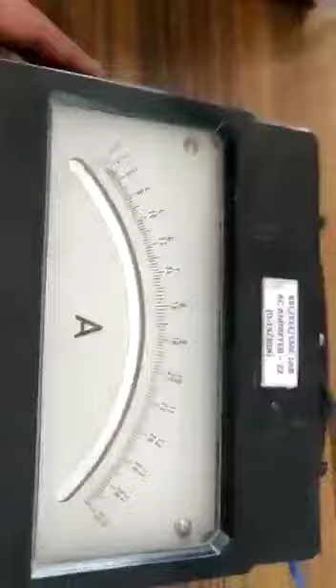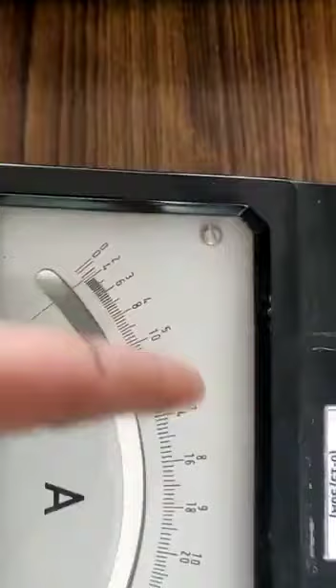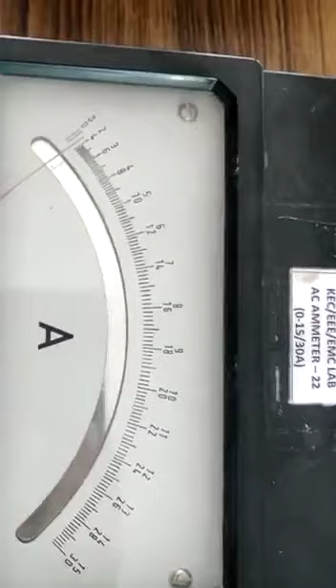Now for the second reading we will see. I am varying the load. Load has been changed. Now this is the reading of CT, that is 0.26 into 10, 2.6 amps. 2.6 amps, but actual current is 2 amps only. We have to look at the top because it is a 0 to 15 amp scale. When you are swinging at the top, this is 2 amps. So 0.6 amps is the difference in the upper side with respect to CT.